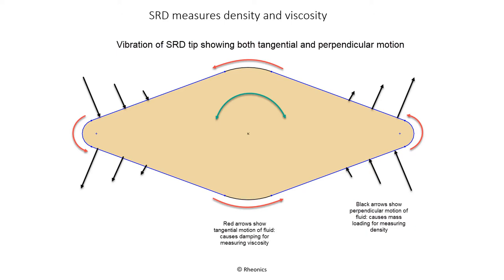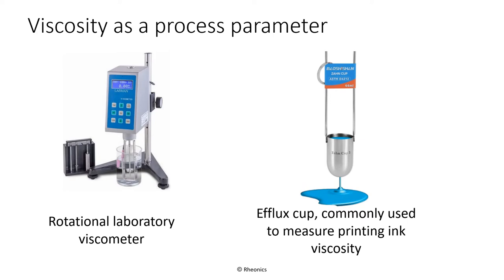SRD's diamond-shaped paddle pushes fluid ahead of it as well as shearing the fluid. Perpendicular fluid motion, shown by the black arrows in the diagram, causes mass loading of the resonator, decreasing its frequency. The red curved arrows show how the SRD's resonator also causes fluid shearing, leading to viscosity-dependent damping. Measuring frequency and damping of the resonator gives both density and viscosity of the fluid.